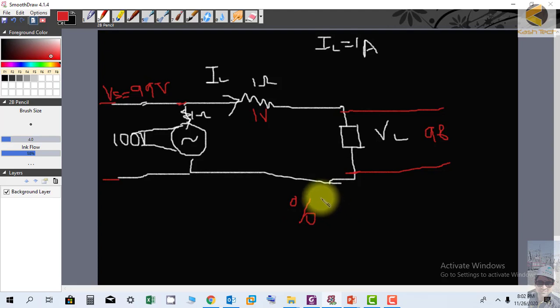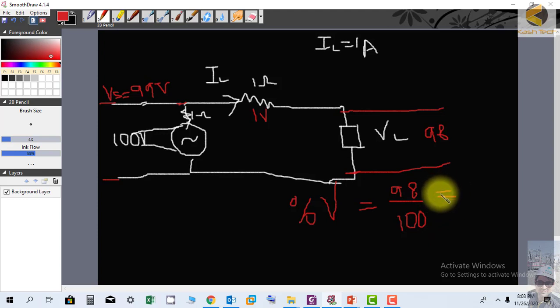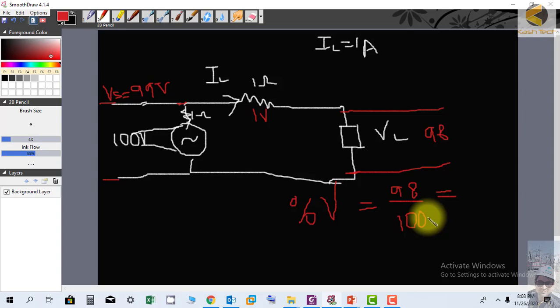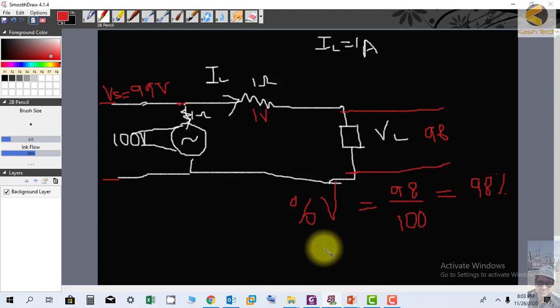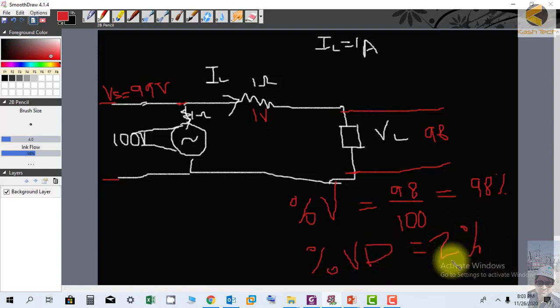The rated voltage of this network is 100 volts, but we are supplying 98 volts at one ampere. The percentage voltage applied equals 98 divided by 100 multiplied by 100, which is 98%. Therefore, the percentage voltage drop is 2% — one percent each dropped across the line and the source impedance.